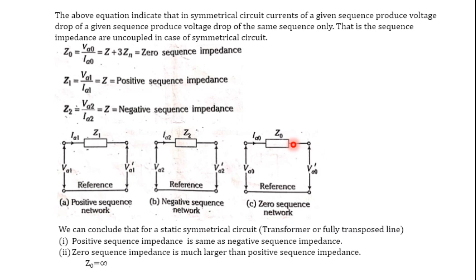For a static symmetrical circuit — such as a transformer or a fully transposed transmission line — the positive sequence impedance is the same as the negative sequence impedance. However, the zero sequence impedance is very large compared to the positive sequence impedance. If there is no neutral connection, Z0 becomes infinite. That is why the neutral plays an important role when dealing with zero sequence impedance, voltage, and current.